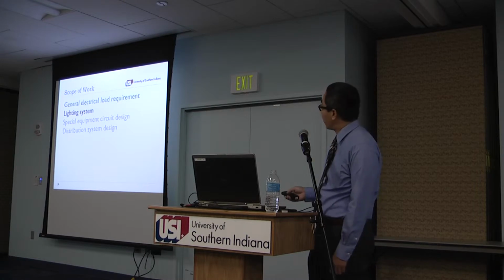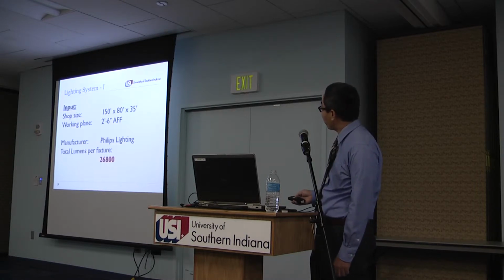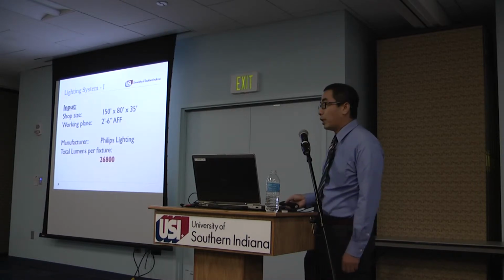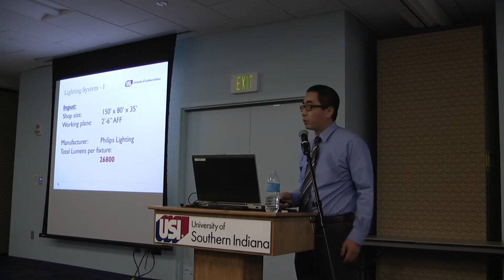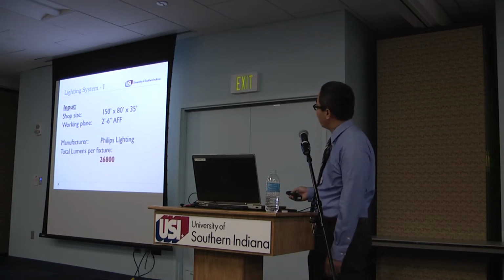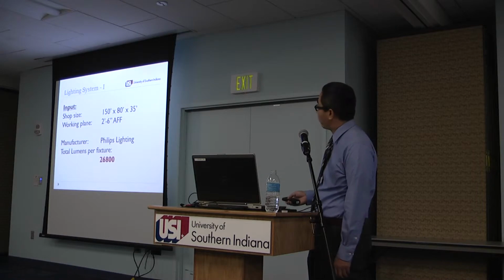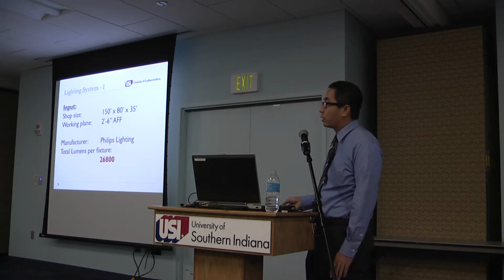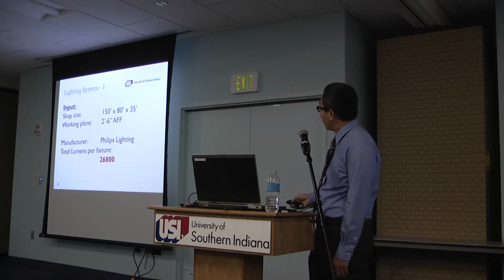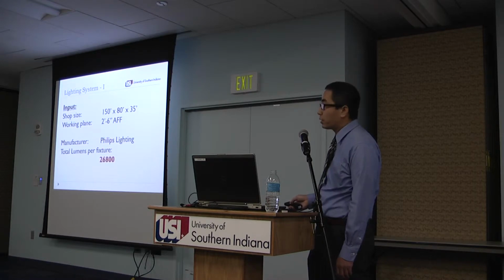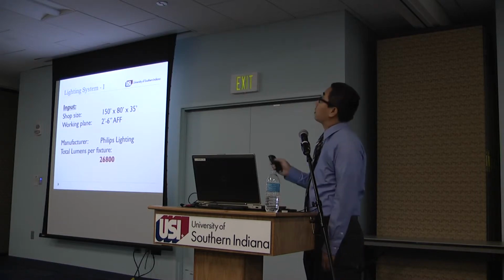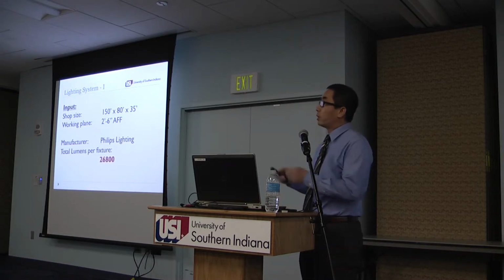The next one will be the lighting system design. The input for the lighting system is basically the geometry, the size of the building, where is the working surface. For this one, our working surface is 30 inches above the floor. And we use Philips lighting, the fluorescent lighting. Each lighting fixture has 26,800 lumens. So that's the light coming out from the lighting fixture.